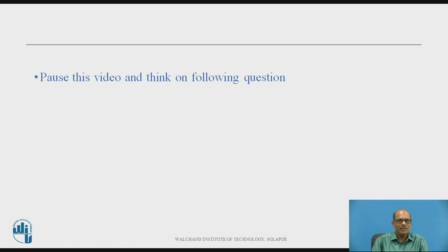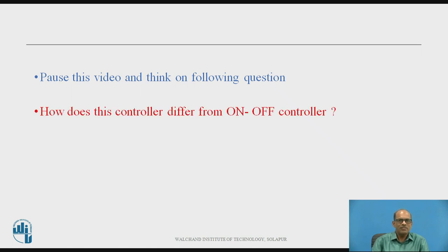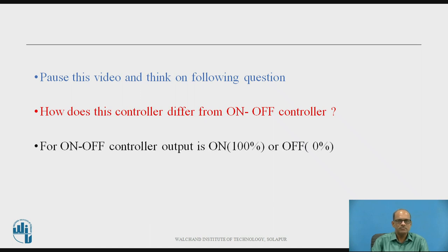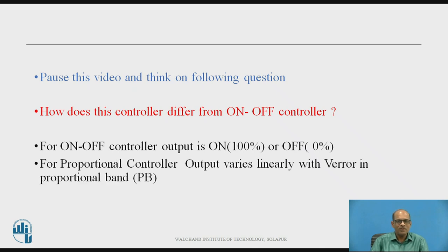Now pause this video and think about the following question: how does this controller differ from an on-off controller? Basically, in an on-off controller, the controller output is either on or off. When the controller output is on, it is 100%, and when it is off, 0% power is delivered to the load. For the proportional controller, the output varies linearly with V-error — that is, the error voltage — within the proportional band.